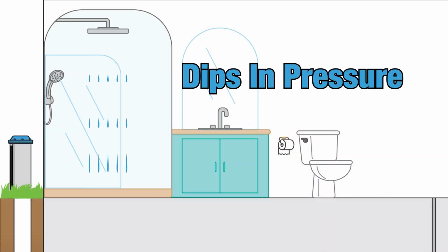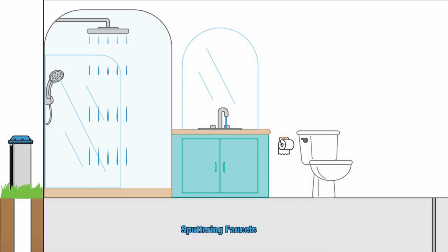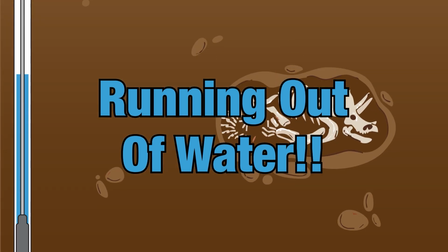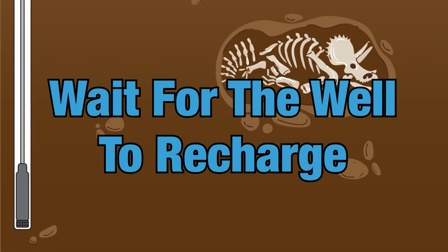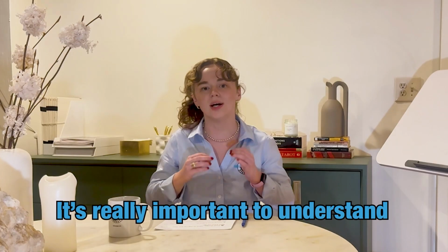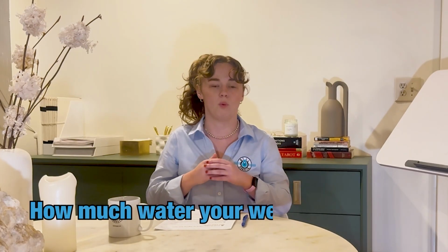If you don't have a low yielding well, which is anything below 3 gallons per minute, that means that your well can almost always keep up with the demands of the household, and you're not going to be running into a situation in which you might want to check this. However, if you're seeing dips in pressure, you're noticing sputtering faucets, or you're actually running out of water and having to wait for the well to recharge, it's really important to understand just how much water your well can produce over a given amount of time.